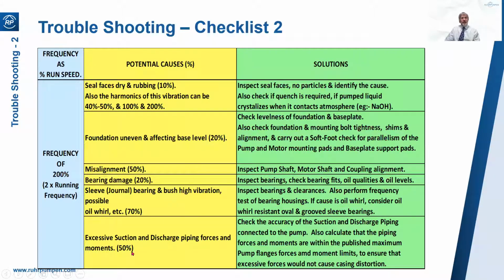Yeah, 50% of the time it's excessive piping forces and moments. So that's the first thing to check. Check your suction and discharge piping connections. And the other 50% of the time it's misalignment. So again, inspect your alignment.